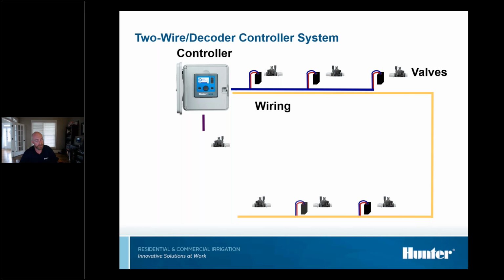So here's the decoder here, and I'm going to show you, if I can get this tie off of it, that on one side you've got your leads, your red and blue leads from the wire path. If you guys can see that. Then on the other side, you've got your black leads that go out to your solenoid. So as you can see in this diagram, you've got your 2-wire leads tied into the 2-wire path, and your black leads go out to the solenoid.